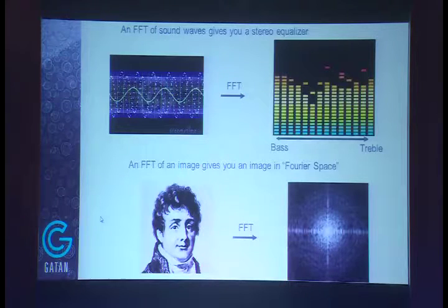I'm not going to go into much detail about DQE, but I just want to give you a quick pass through it. The way we think about DQE is we always think in Fourier space. In this audience, maybe many of you are very comfortable thinking in Fourier space. For those of you who might not be, if you think of a sound wave and you look at the FFT of the sound wave, that's what you see as the bass and the treble in the equalizer of your stereo system. You have lots of bass components, low frequency components, and lots of treble components, the high frequency components.